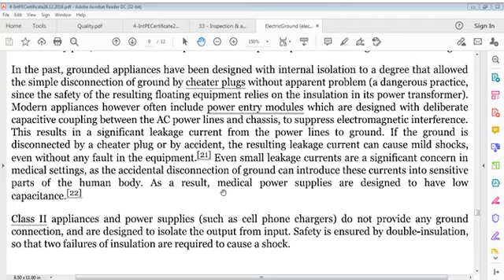If ground is disconnected by a cheater plug or by accident, the resulting leakage current can cause mild shocks even without any fault in equipment. Even small leakage currents are a significant concern in medical settings, as accidental disconnection of ground can introduce these currents into sensitive parts of the human body. As a result, medical power supplies are designed to have low capacitance.